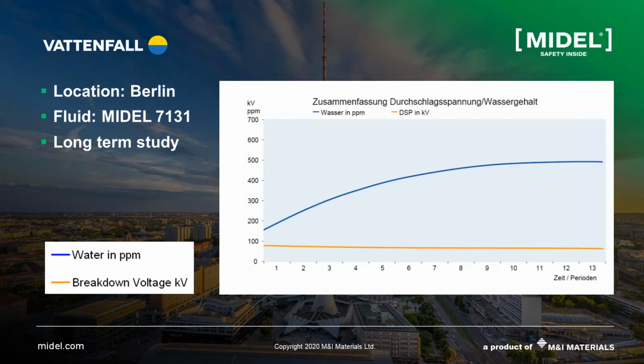As part of this wide study, world-class utility Vattenfall also evaluated what happened to both the moisture content and its relationship to electrical strength, recognized as breakdown voltage, over a long 13-year period. You can see the blue line steadily increases. This is because of the polar nature of the ester slowly migrating moisture from the solid insulation to the fluid, while significantly slowing down the aging process. MIDEL can handle moisture much better than mineral oil, shown on the yellow line, where breakdown voltage was almost completely unaffected over the 13-year assessment. It remained electrically strong throughout.